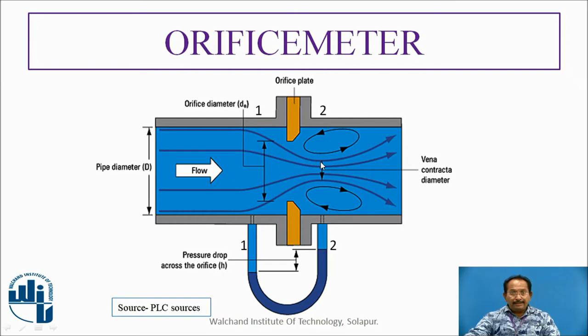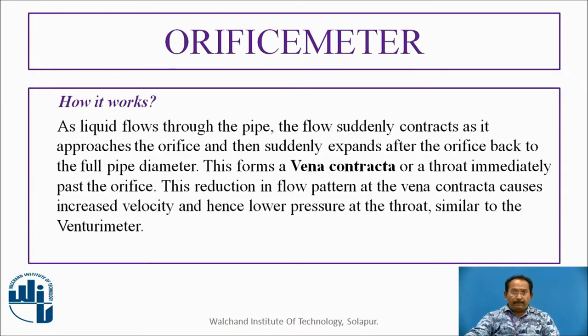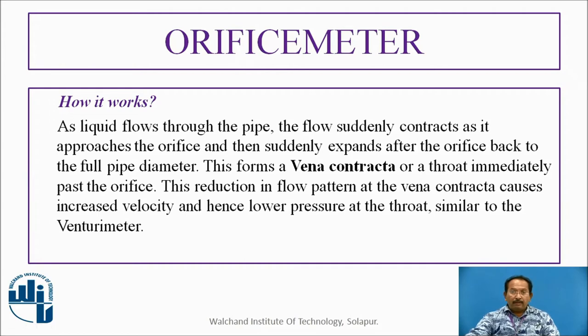This is a simple figure and the manometer is attached, showing the difference in the manometric liquid, similar to what we have done for the Venturimeter. A liquid flows through the pipe; the flow suddenly contracts as it approaches the orifice plate and then suddenly expands back to the full pipe diameter. This forms a vena contracta, or throat, immediately past the orifice. This reduction in flow at the vena contracta causes increased velocity and hence lower pressure at the throat, since velocity and pressure are inversely proportional — the same as seen in the Venturimeter.